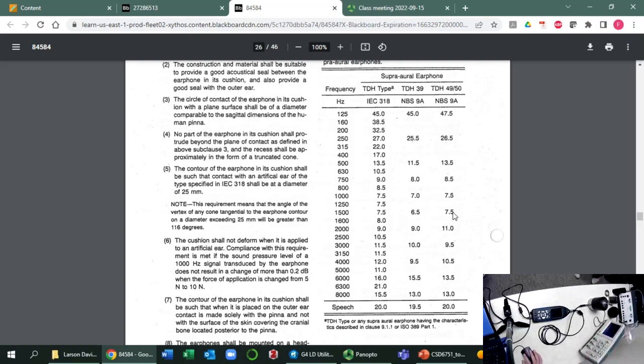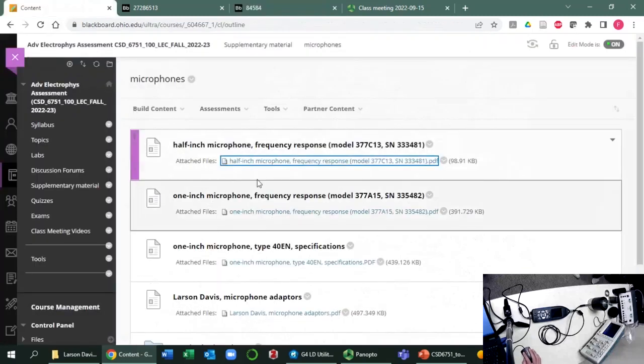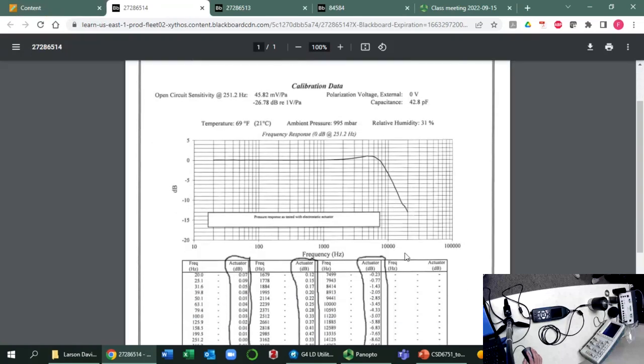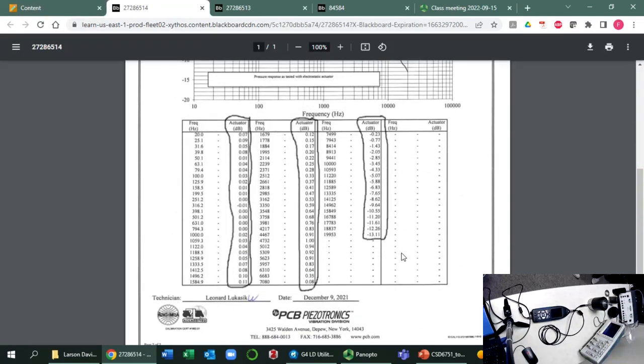Okay. So then we go back to the supplementary material and open the 1-inch microphone frequency response chart. And of course, we scroll down and look at the actuator column for 2000 Hertz. Oh no, not 2000 Hertz. And of course, we find the one that's closest. So 1995, the correction factor is 0.20. So then we have 60 plus 11 plus 0.20. Am I right? So that's 71.2.